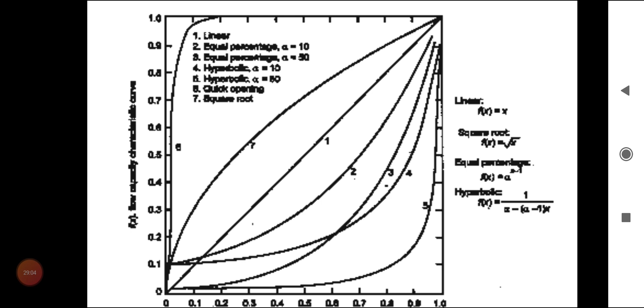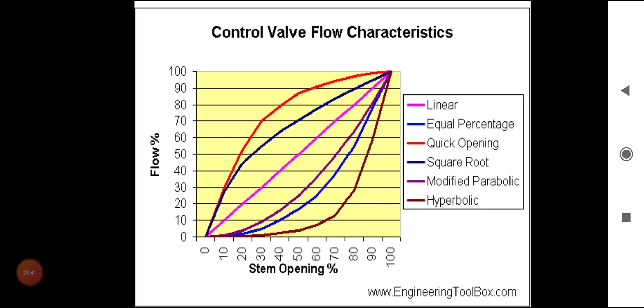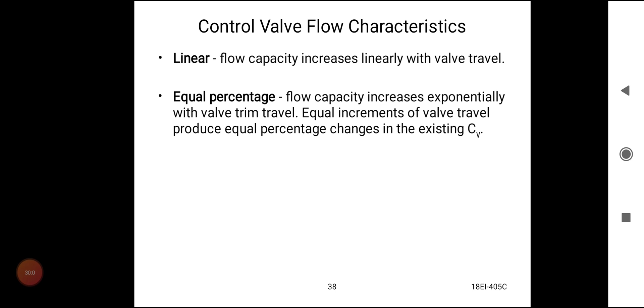The control valve flow characteristics: the pink shows linear, the blue shows equal percentage, the red shows quick opening, and square root and modified parabolic, hyperbolic as shown in the slide. The graph shows stem opening percentage against valve flow rate. For linear, flow capacity increases linearly with valve travel. For equal percentage, flow capacity increases exponentially with valve trim travel. Equal increments of valve travel produce equal percentage changes in the existing Cv.